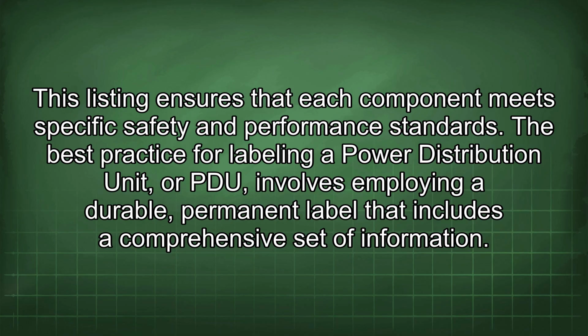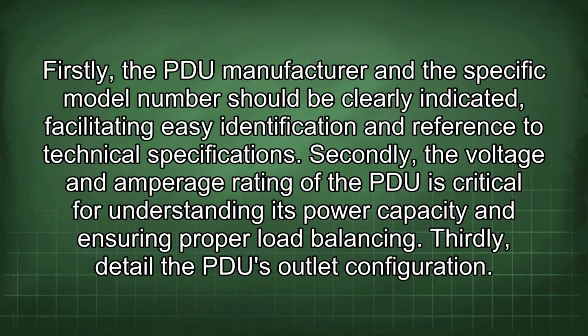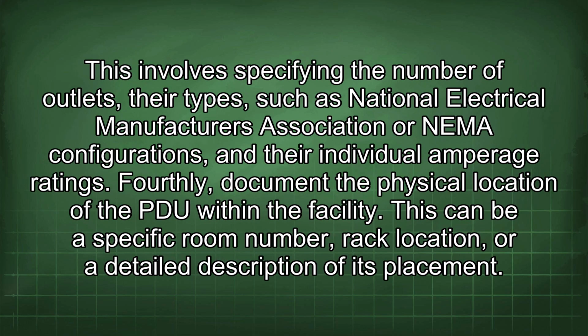The best practice for labeling a power distribution unit, or PDU, involves employing a durable, permanent label that includes a comprehensive set of information. Firstly, the PDU manufacturer and the specific model number should be clearly indicated, facilitating easy identification and reference to technical specifications. Secondly, the voltage and amperage rating of the PDU is critical for understanding its power capacity and ensuring proper load balancing. Thirdly, detail the PDU outlet configuration.